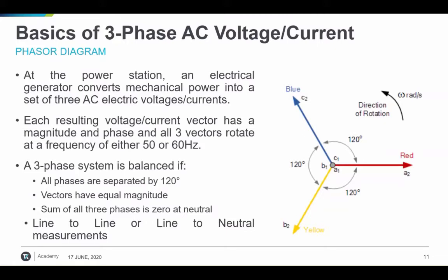If you want to make a measurement between these three phases, there are different configurations you can use. You can measure between the lines — for example, between A and B — which gives you a line-to-line voltage measurement. Or if you want per-phase measurements, you make a connection between the line and the neutral if it's available. Keep in mind there will be vectors for both voltages and currents, with some angle between them. We'll look at phasor diagrams more in the demo.